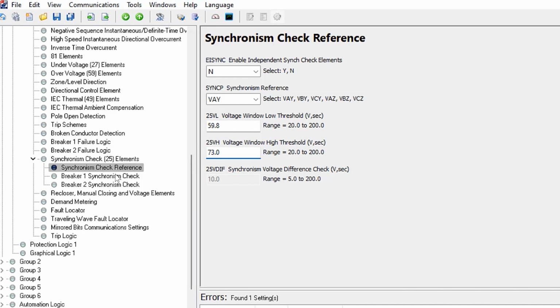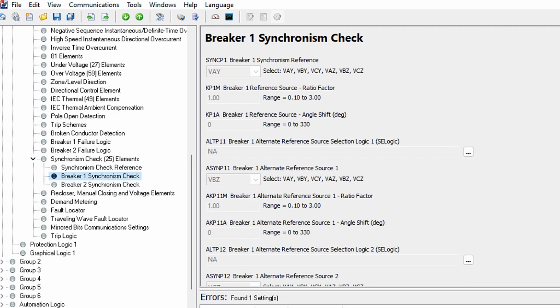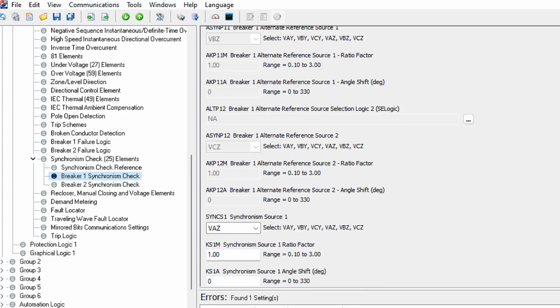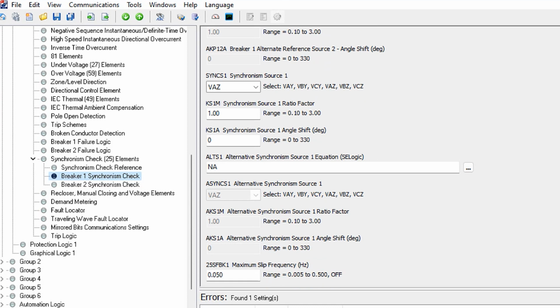Now we can go here to breaker 1 synchronism check. So now that we've defined a reference, we also need to set the sync check settings for the bus 1 side. So let me scroll down over here, and that's down here under synchronism source. And again, here I said that the bus side voltage for bus 1 is connected to the VAZ input of the relay. So that's why we can use the default setting over here, which is VAZ.